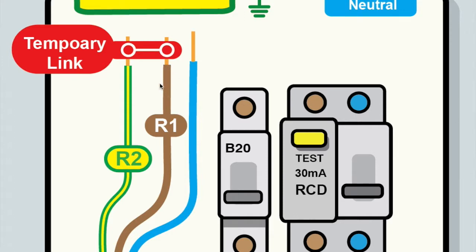You can see here the temporary link where we've linked together the CPC and the line conductor to enable our testing. When we're testing we give these conductors a name. The CPC is known as the R2, the line conductor is known as the R1.